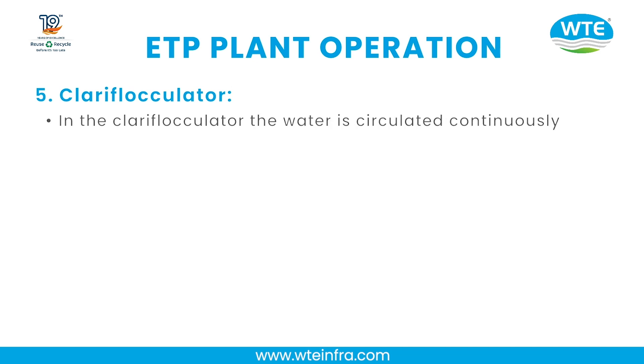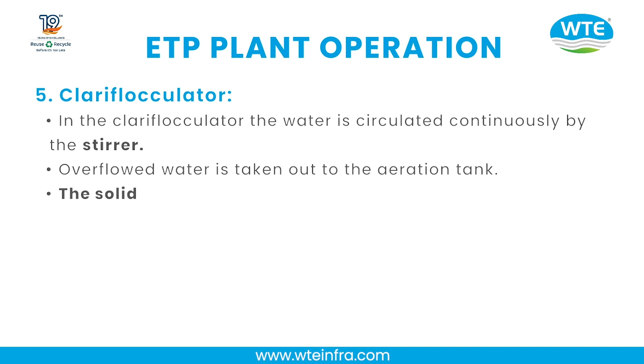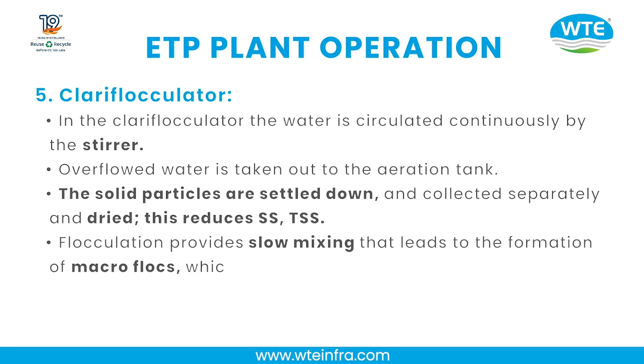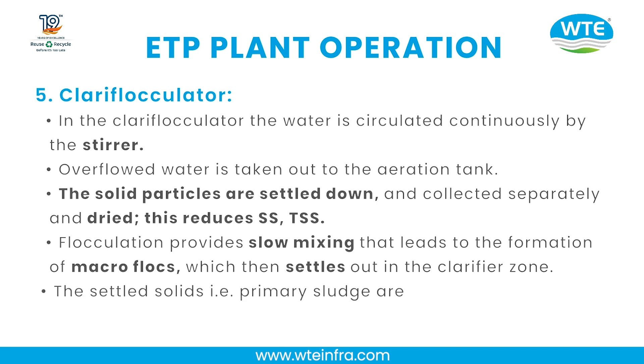Step 5 — Clariflocculator: Water is circulated continuously by a stirrer. Overflowed water is taken out to the aeration tank. Solid particles settle down and are collected and dried, reducing TSS. Flocculation provides slow mixing that leads to the formation of macro flocs, which then settle out in the clarifier zone. The settled solids (primary sludge) are pumped into the sludge drying beds.